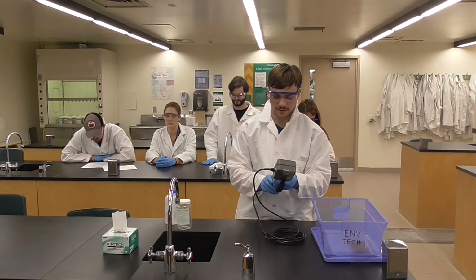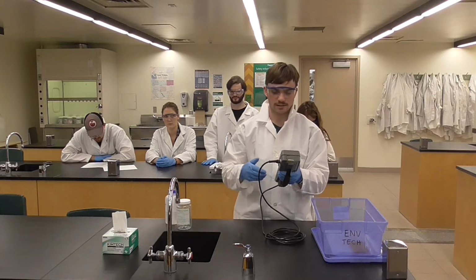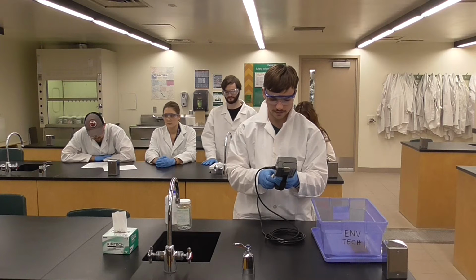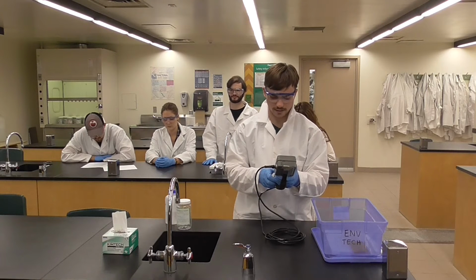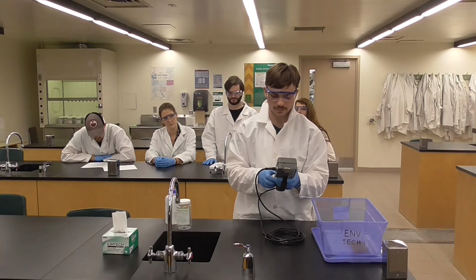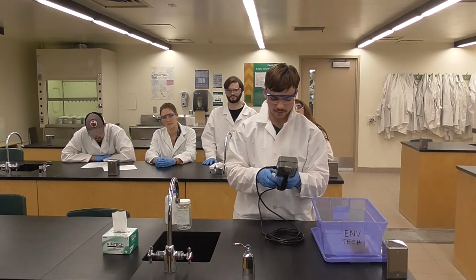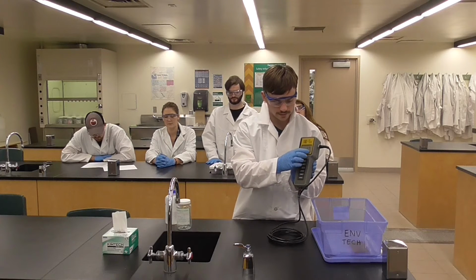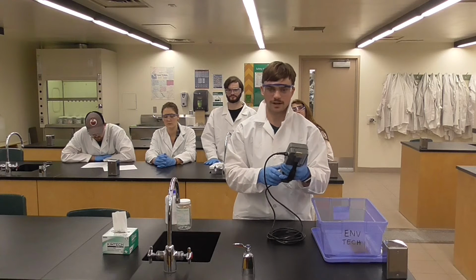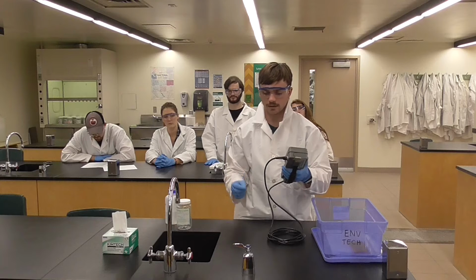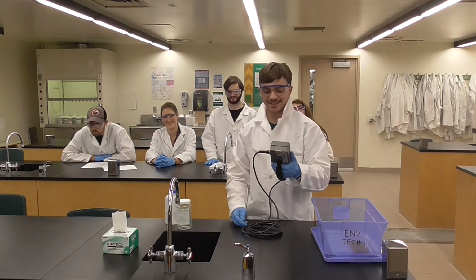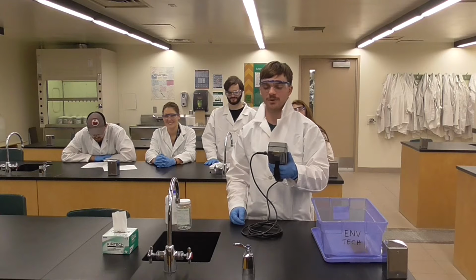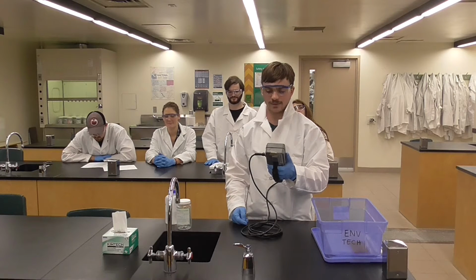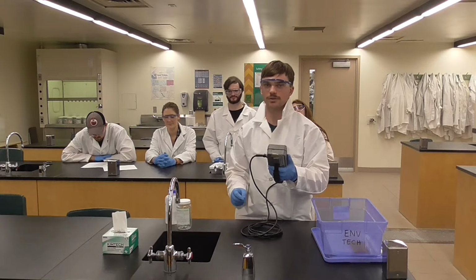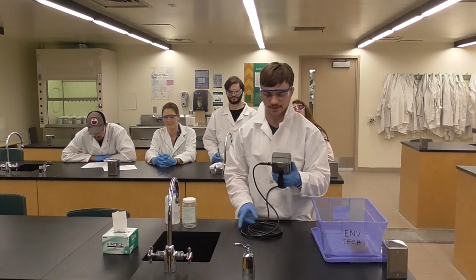Next, I'm going to turn the meter on and then make sure it is set to specific conductance. You'll know when it's set to that when the degrees C is flashing on the temperature reading. I'm going to press mode until I can see the degrees C flashing. The specific conductance will measure the conductivity of the water at what it would be at 25 degrees Celsius, whereas the conductivity measurement will measure the water at the actual temperature of the sample.